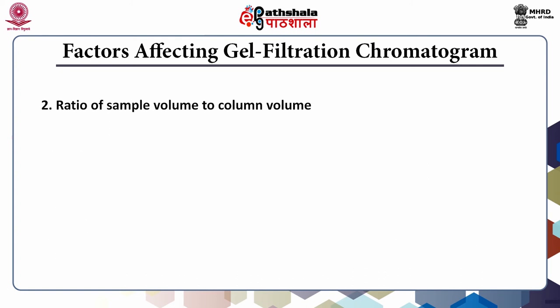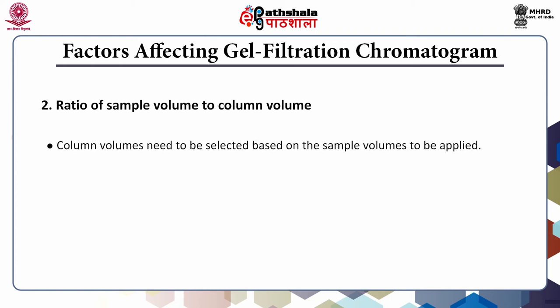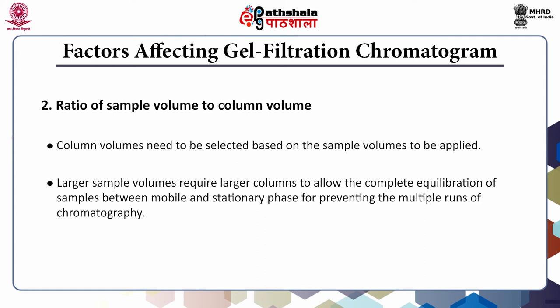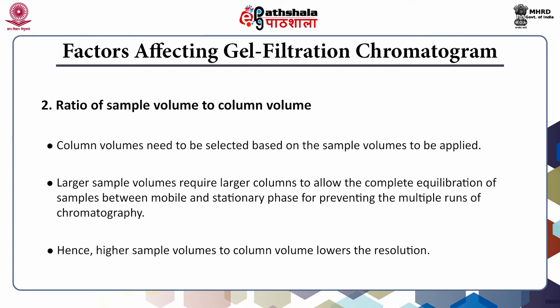The second factor is the ratio of sample volume to column volume. Column volumes need to be selected based upon the sample volumes to be applied — these two are interrelated. Larger sample volumes require larger columns to allow complete equilibration of samples between mobile and stationary phase, preventing multiple runs. Higher sample volumes to column volume lowers the resolution, which is why only 0.5 to 4 percent of the column volume should be used as sample volume.